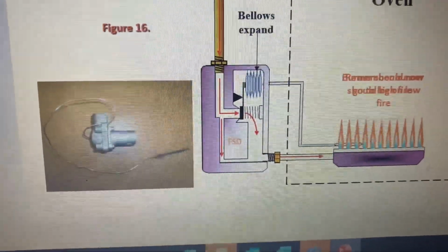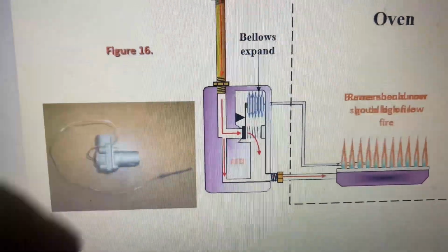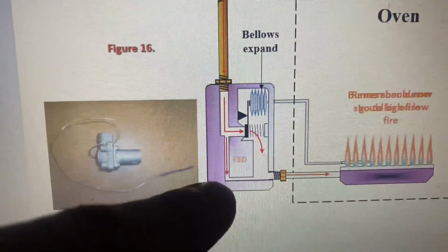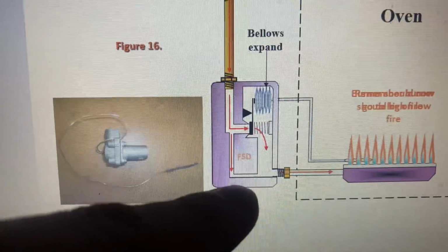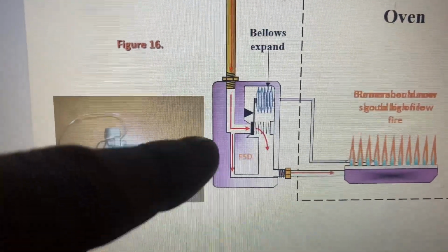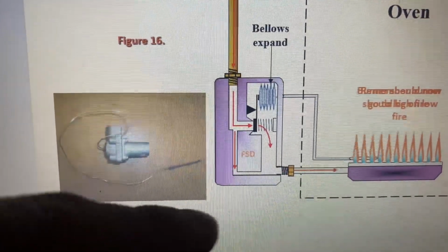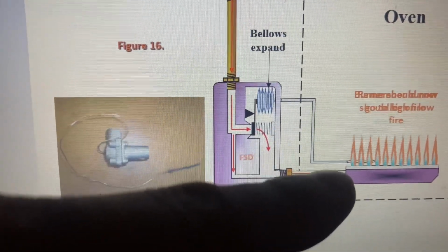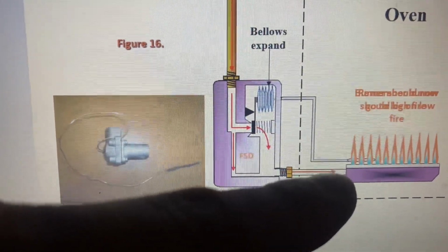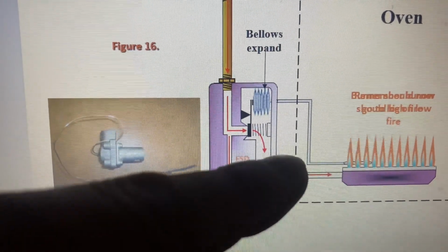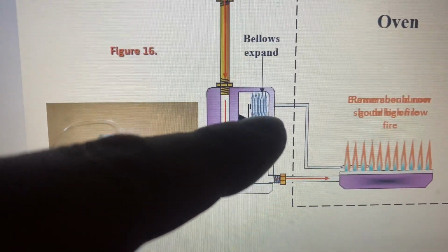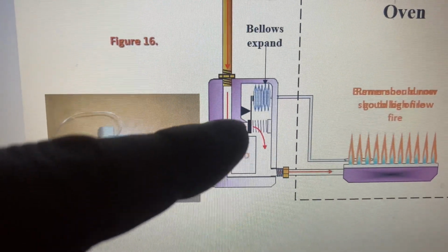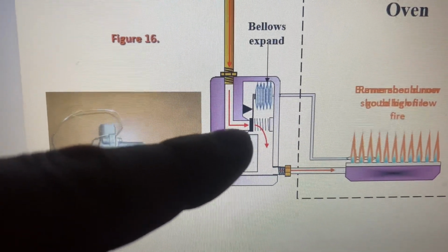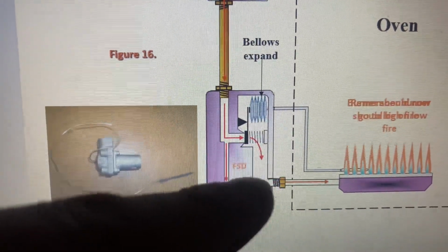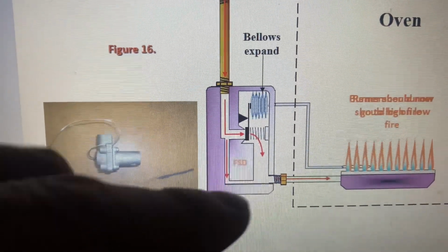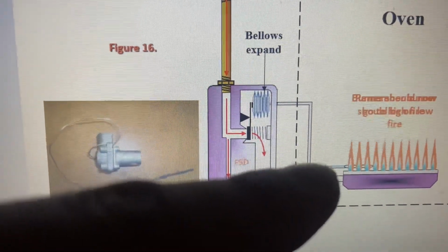This is a picture of the burner, and this really highlights how dangerous ovens can be. So the bypass comes down along. So the bypass always lets gas through to the burner so it can be ignited and it'll always stay lit. There's the flame safety device. You can see the flame safety device in the flame. It goes across and it opens up that bellow, that diaphragm. So if you're getting a small flame but it's not lifting, it's a flame safety device.